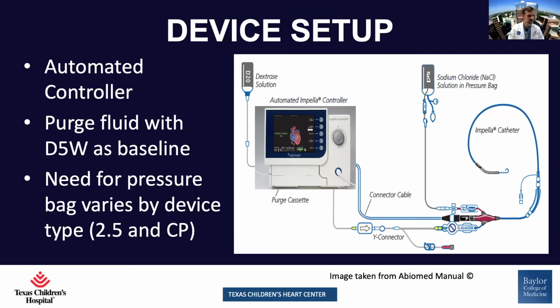Most importantly, the device requires what's called a purge solution, and the whole purpose of the purge solution is to maintain lubrication of the motor at the end of the device, as well as protect the motor from any blood going into it. The purge solution is set right at the automated Impella controller. It regulates how much fluid is going into the patient through the purge side arm of the catheter. This is provided at an increased pressure, so the device generates certain pressure to inject that purge solution into the motor. Typically the purge solution is composed of dextrose without any saline in it, so it would typically be a D5W solution at baseline.